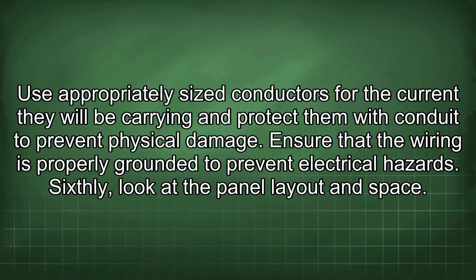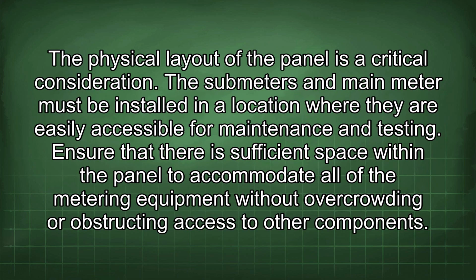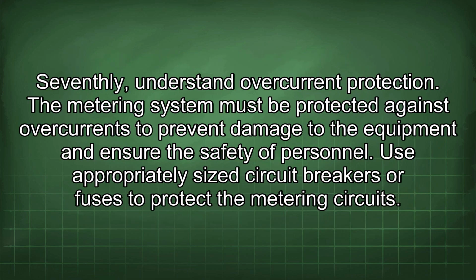Sixthly, look at the panel layout and space. The physical layout of the panel is a critical consideration. The submeters and main meter must be installed in a location where they are easily accessible for maintenance and testing. Ensure that there is sufficient space within the panel to accommodate all of the metering equipment without overcrowding or obstructing access to other components.